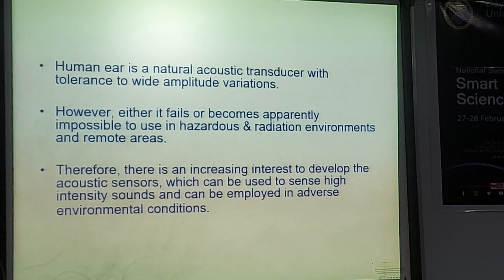However, it either fails or becomes impossible to use in hazardous and radiation environments and remote areas. Therefore, there is an increasing interest to develop acoustic sensors which can be used to sense high intensity sound and can be employed in adverse environmental conditions. With this in view, we developed some acoustic sensors. Typically, the transduction principle used in acoustic sensors can be based on piezoelectric, piezoresistive, or capacitance phenomena. What we have chosen is the principle of the piezoelectric effect, carrying out the development and study of a low-cost thin film acoustic sensor suitable for high-intensity sound up to 150 dB. So, we developed the acoustic sensor based on piezoelectric thin film to convert the acoustic signal into a proportional electrical output.